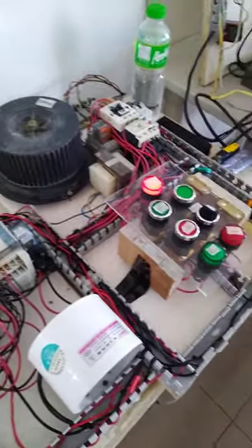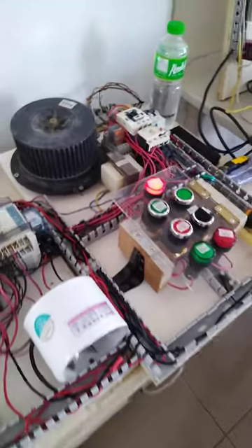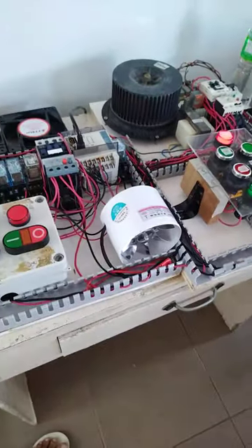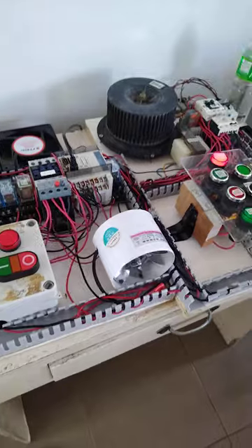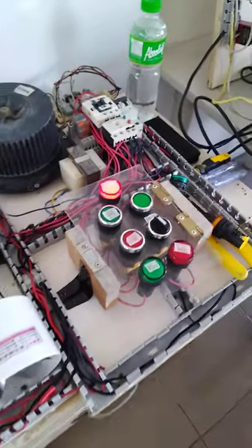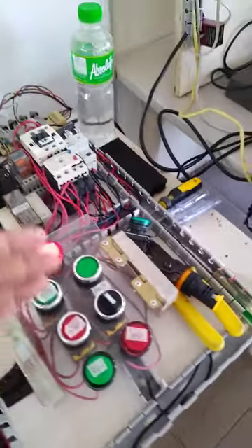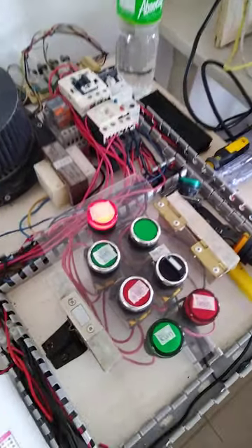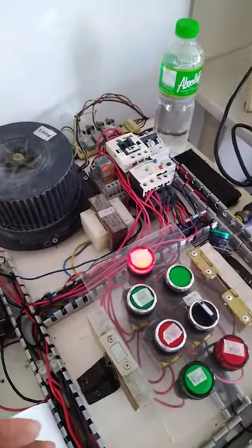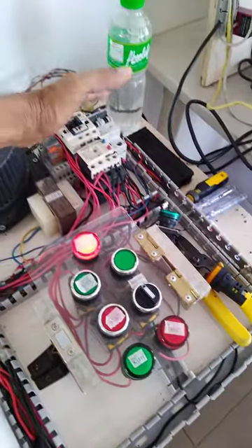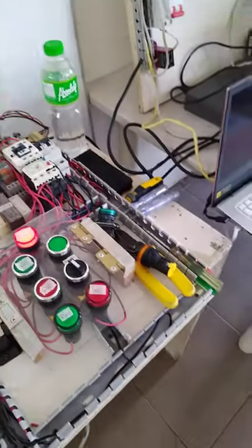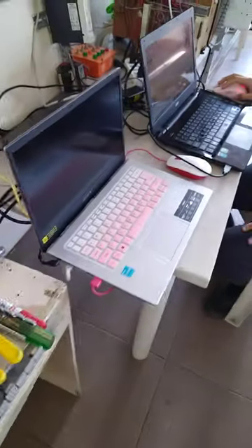So today we are going to show them how you are going to solve this problem if you encounter this problem in the site. What we are going to do is, in our building or in our plant, we need to start all these fans. But since our circuit breaker is not capable of handling the inrush current, we are going to program these fans to run every five seconds.